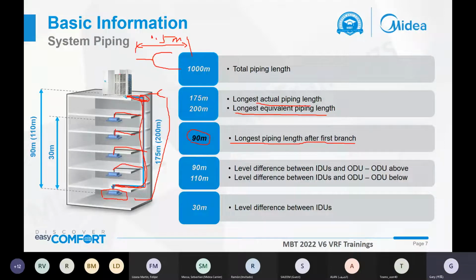And when the outdoor unit is installed on the top, we can have a 90 meters height difference between the outdoor unit and the indoor unit. If the outdoor unit is on the floor, we will have 110 meters between the indoor unit and the outdoor unit. And for each indoor unit, the level difference should be less than 30 meters.